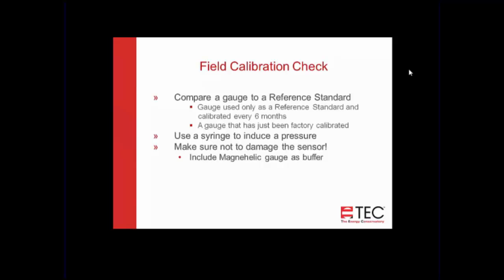One of the downsides of Magnehelic gauges is over time they get leaky and they won't hold pressure. So then you can apply the pressure from a syringe, but you won't be able to hold pressure. So that method has a downside. So we came up with a new method that uses a 1 milliliter syringe and 30 feet of tubing. It's important to have that 30 feet of tubing on there, so that acts as the buffer, so you don't overpressurize with that small syringe.